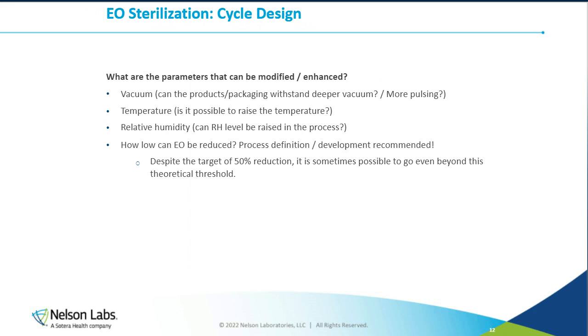So what can we modify or improve in a cycle? The vacuum is one of the critical elements, because as deep as we can go, the better penetration of gas will be, but it may have an impact on the packaging and also on the product resistance. Just giving you an example, pre-filled syringes cannot withstand deep vacuum because the plunger might be moving, and then you can have leaks in your pre-filled syringe. So it has, of course, some limitations, but we need to review these limitations to see what can be improved.